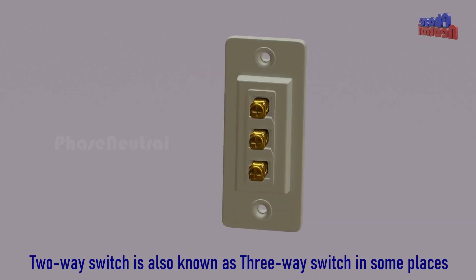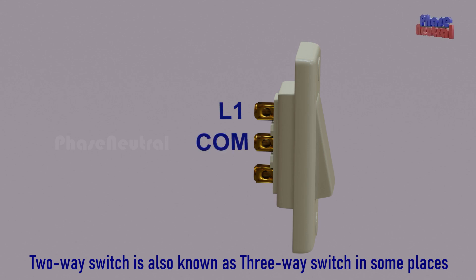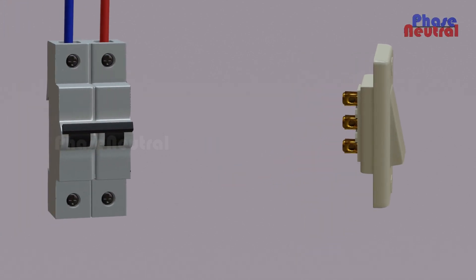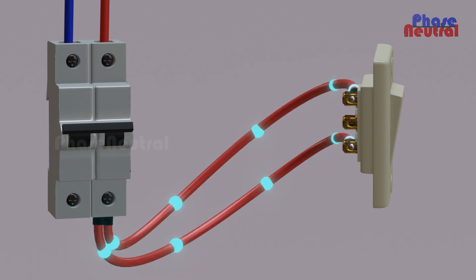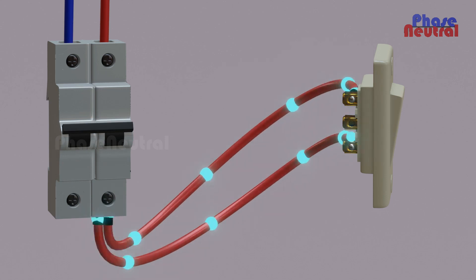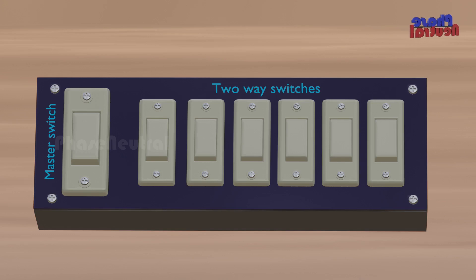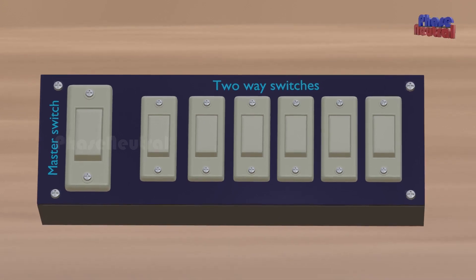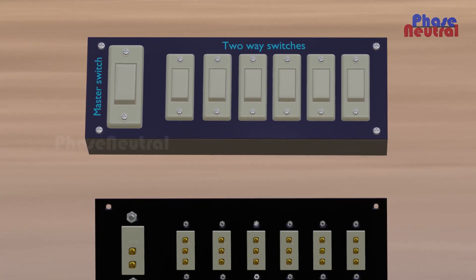Two-way switches have three terminals: L1, common, and L2. If you connect a phase or hot line on both L1 and L2, when the switch is in on position, current flows through L2 to common. And when the switch is in off position, current flows through L1 to common. Because of this feature, we are using two-way switches for the master light switch circuit.